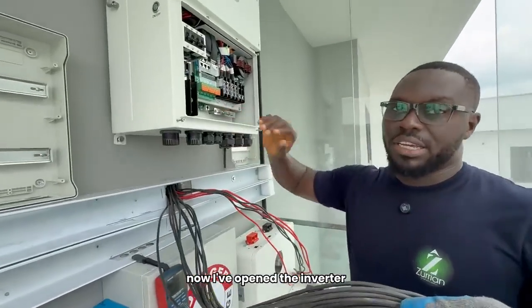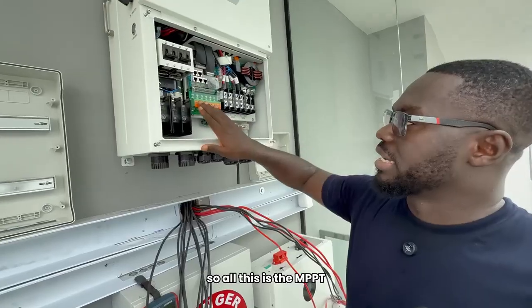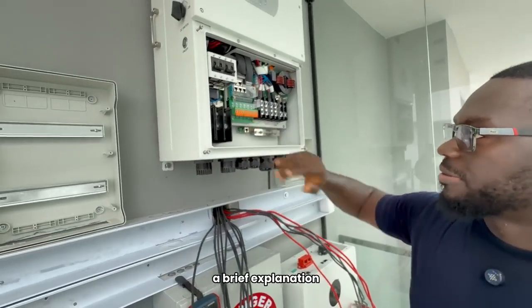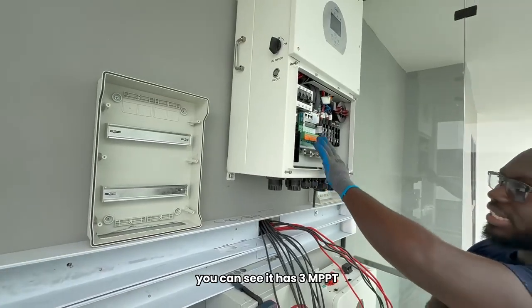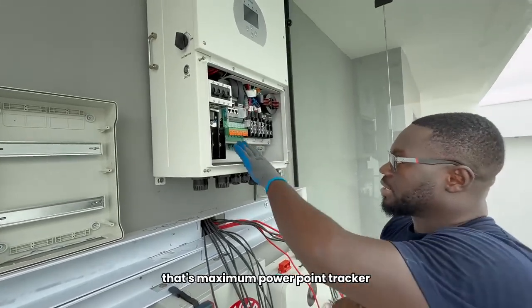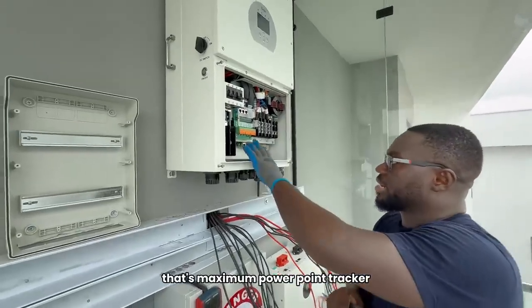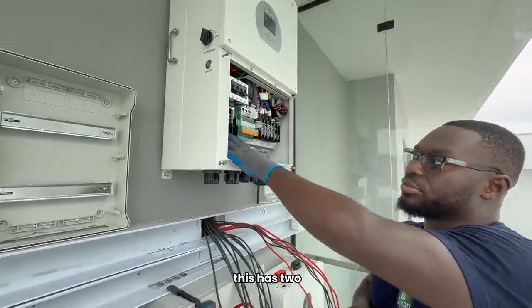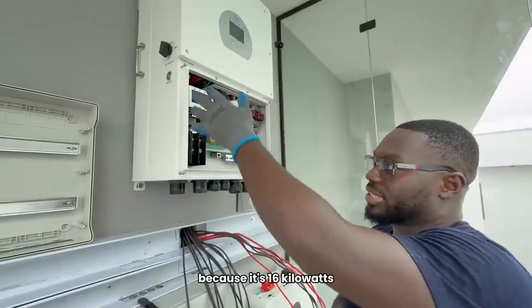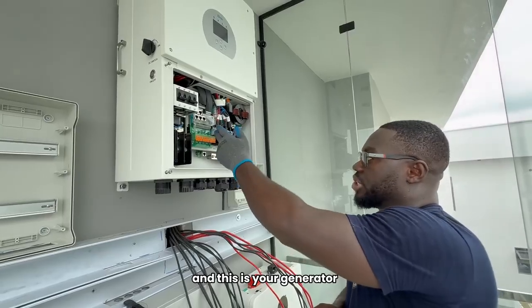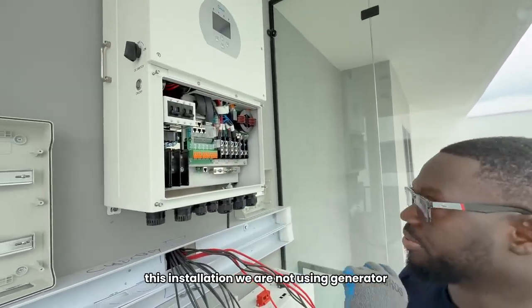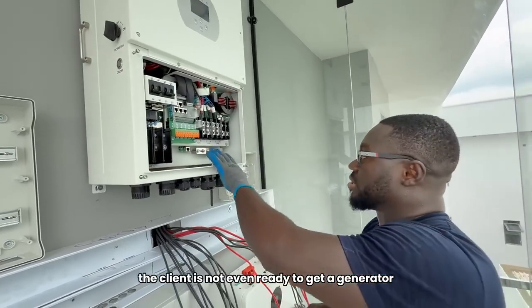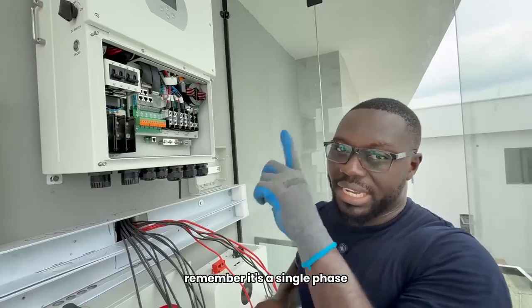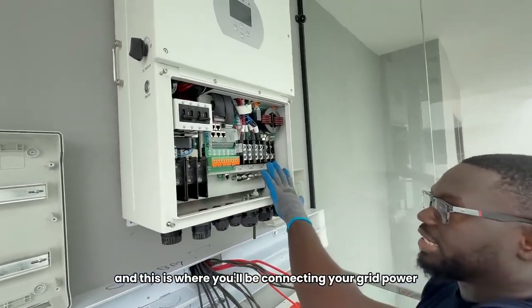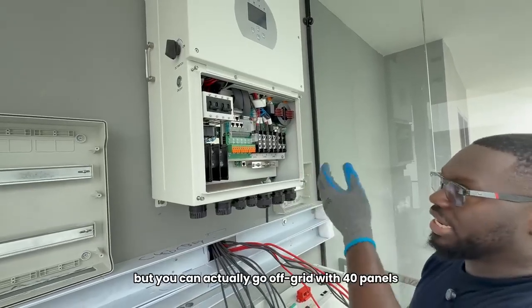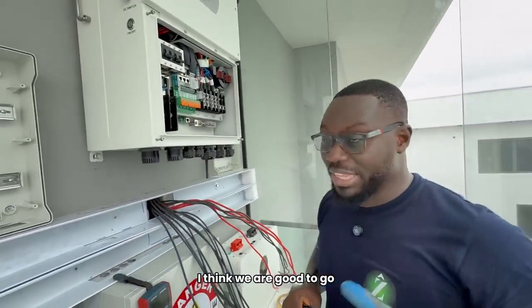Now I've opened the inverter. So all this is the MPPT. If you're familiar with it, a brief explanation. So this is MPPT. You can see it has 3 MPPT. That's maximum power point tracker. So it has 3 MPPT. This has two battery input terminals because it's 16 kilowatts. And this is your generator. For this installation, we are not using a generator because the client is not even ready to get a generator. So this is your output to the house. Remember, it's a single phase, and this is where you'll be connecting your grid power if you need to charge it, but you can actually go off grid with 40 panels. I think we are good to go.